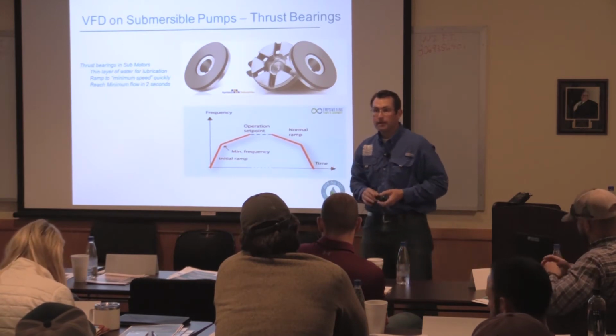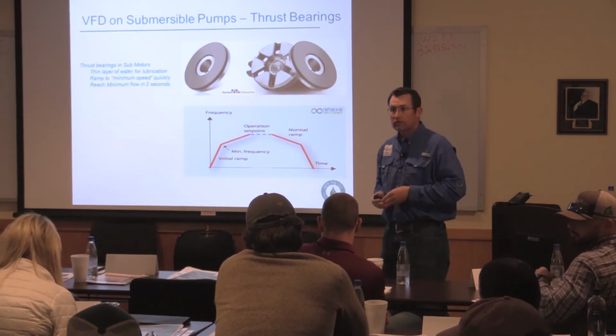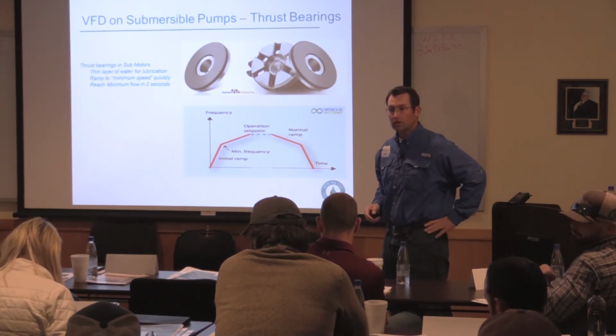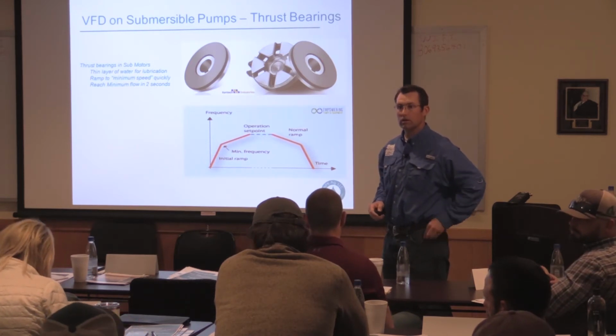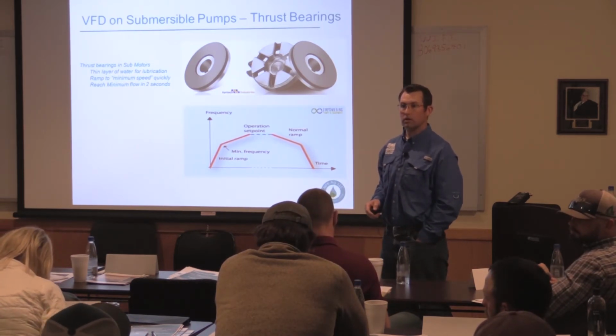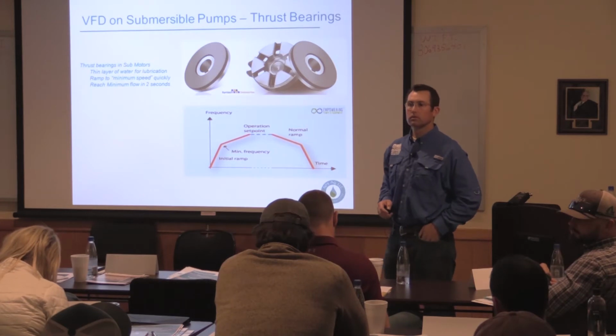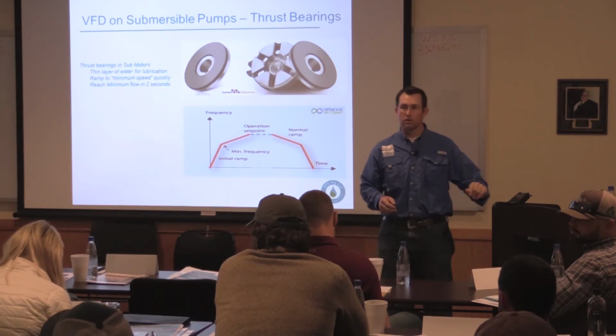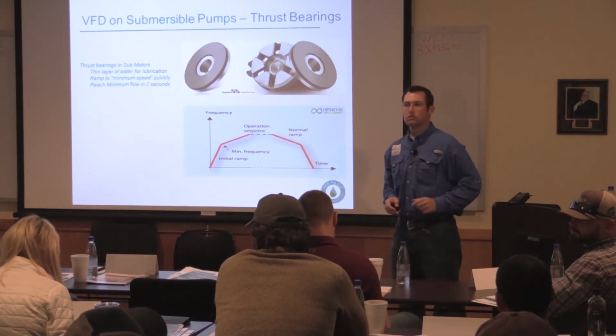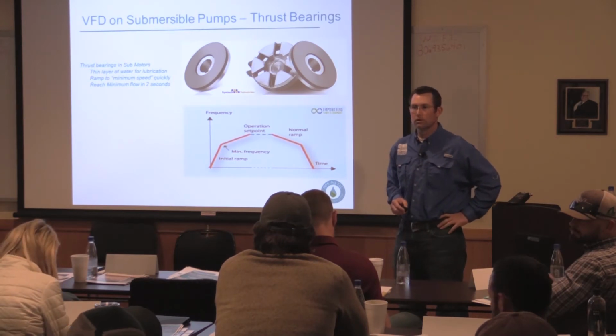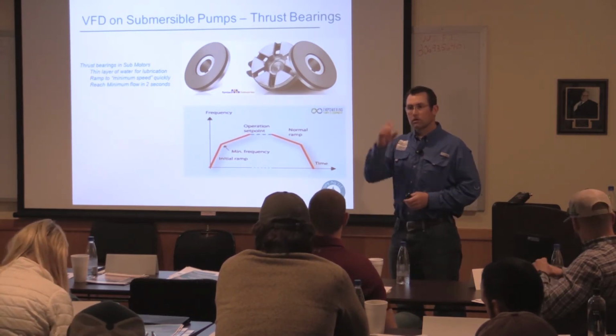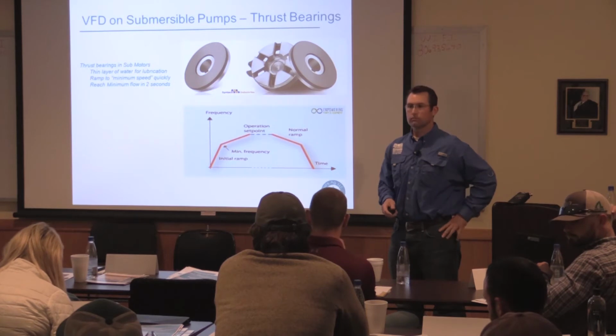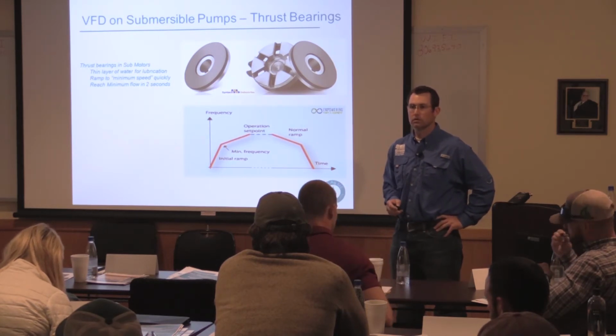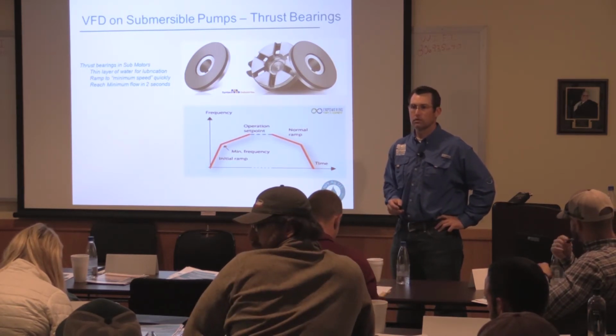Right. One thing to keep in mind on submersibles and VFDs is once you get over 400 foot from the drive, you've got to put a load reactor on. It will make the motor last way longer. We've gotten into situations where we're 600 feet, we're heating motors every 2 years. We put a load reactor on it, and that problem went away.